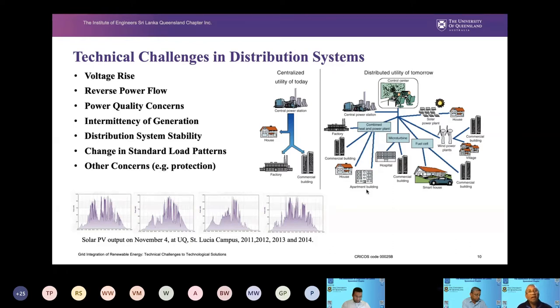And then we had problems of reverse power flow. If you look at the traditional distribution system, those distribution systems were designed to accommodate power in one direction. That means receiving power from the substation all the way to the load. Now, with the integration of PV in the form of rooftop in different households, we are getting reverse power flow as well. That is going to create a lot of problems, including some protection issues and a few other safety concerns as well.